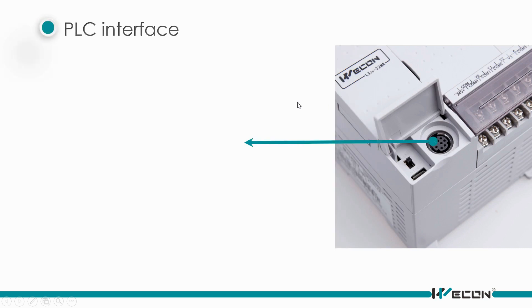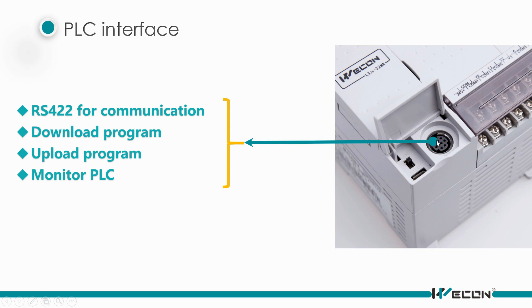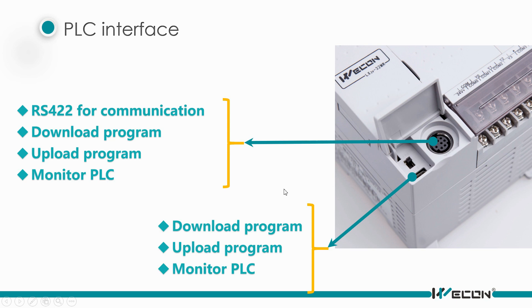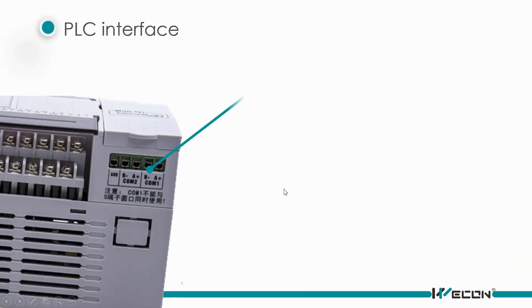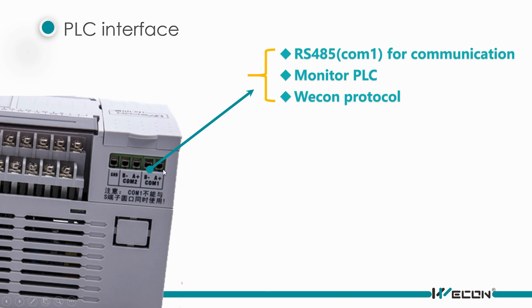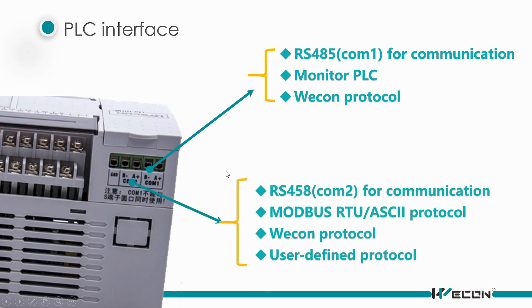Here is the PLC interface. The round connector is the RS422 for communication. There is also a micro-USB port for downloading or uploading programs, and we can also use the micro-USB port to monitor the PLC values. We can also see two RS485 COM ports, COM1 and COM2. COM1 can only support the Wecon protocol, while COM2 can support Modbus, ASCII, and RTU protocols, or the Wecon protocol, or a user-defined protocol.